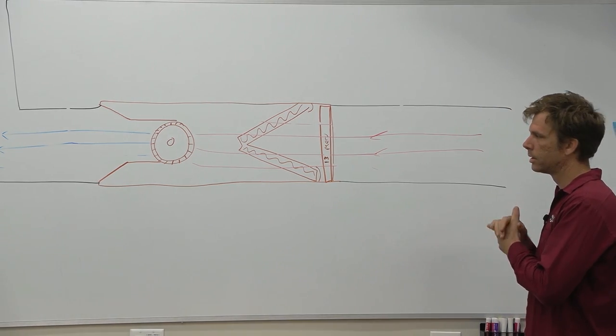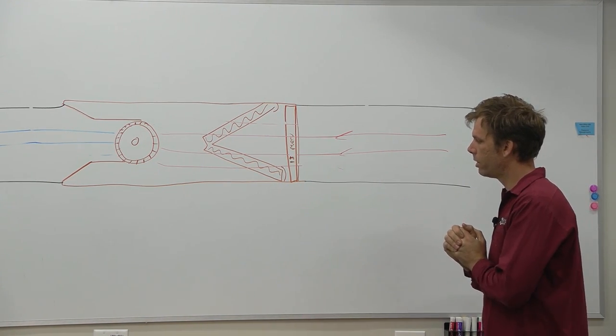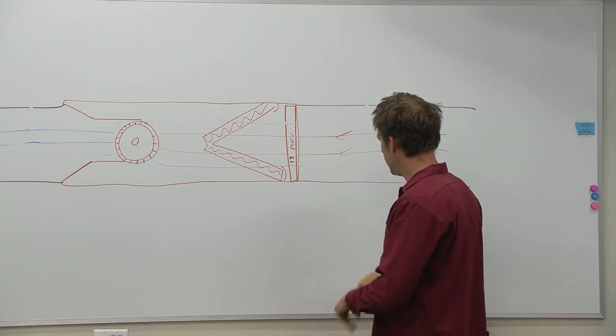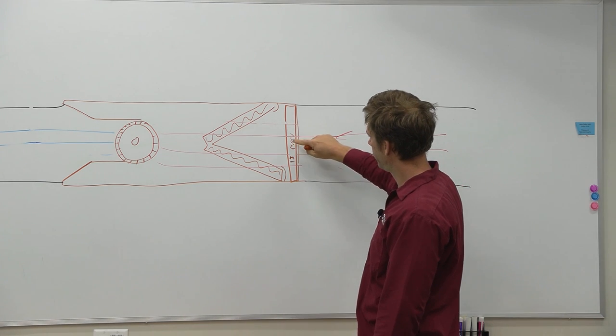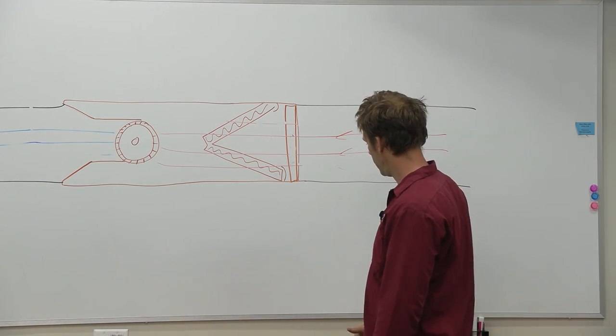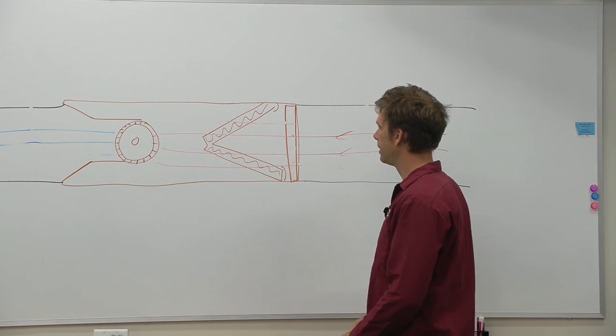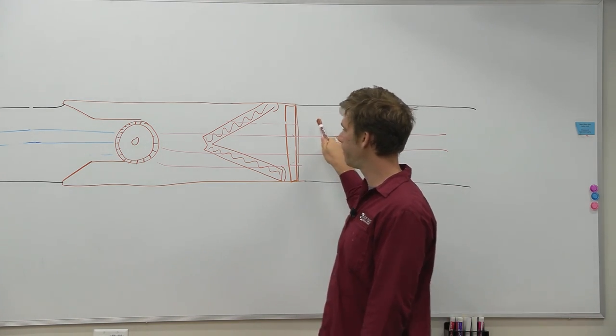When you measure a system's external static, always go above your filter and above the blower in the supply. That's important also for diagnostic.